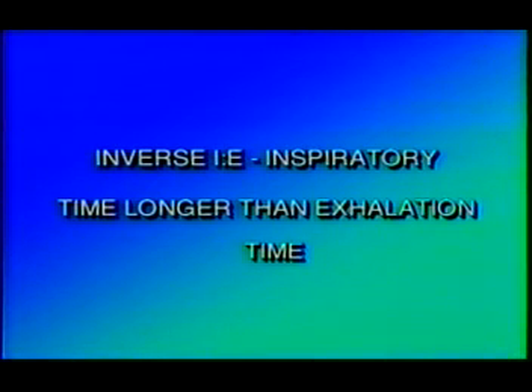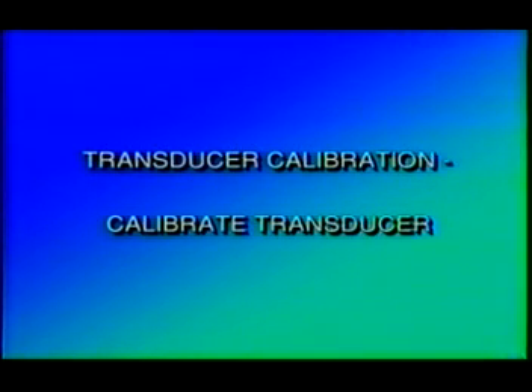Comp. Compressor output, low fail. Inspiration time truncated to 3 seconds. Note I time and IE. Plateau volume. Delivered volume less than set volume. VT settings. I time flow, unable to deliver set volume. External power fail. Disconnect. Check power source. Connections. Inverse IE. Inspiratory time longer than exhalation time. Transducer calibration. Calibrate transducer. Transducer calibration abort. Recalibrate transducer.